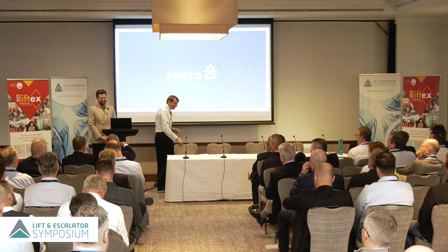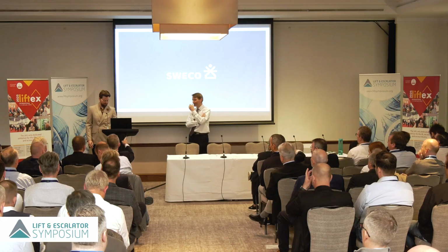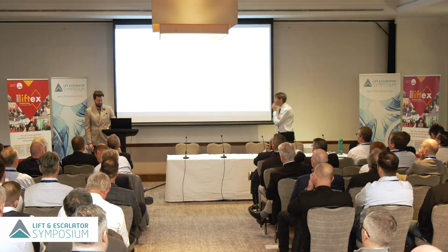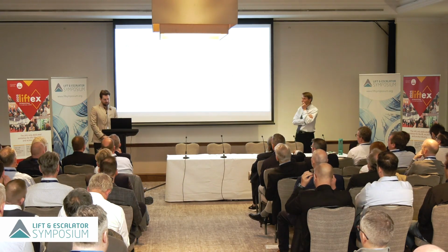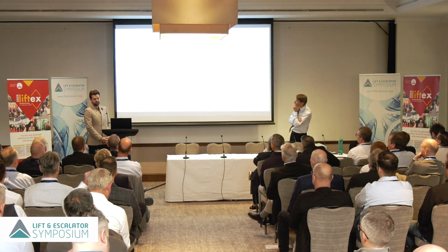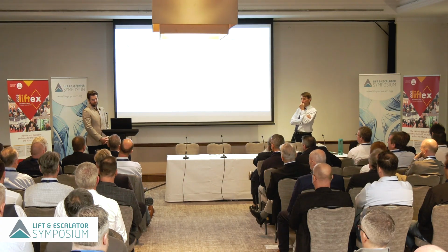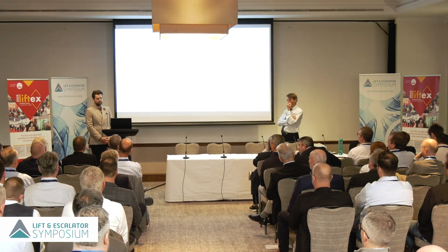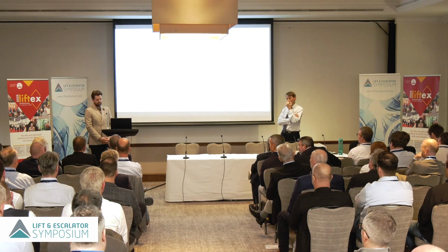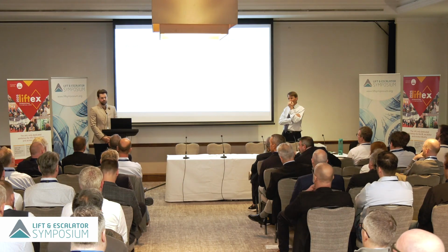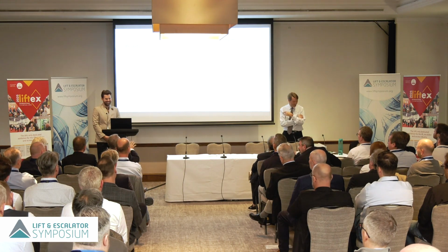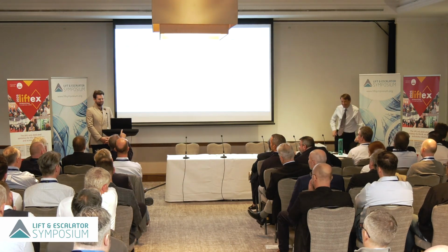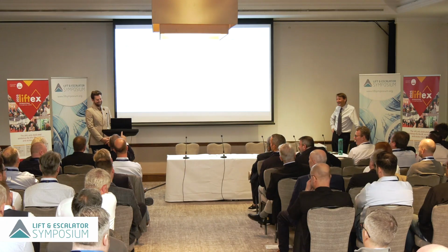Thank you very much. Do you mind if I use your slide to illustrate something? If you go back to your spatial plot. Okay, see that first one, you stop at 34 and 33. I bet the first time round, your lift is full and it doesn't need to stop at 33. It is, yeah. But it's the point I was making. You've got to know whether or not to stop. And of course, we don't know, the lift is weighing the number of people in the car, and that doesn't necessarily correspond, and the bypass is not necessarily set at exactly the right level. You can fiddle it so it works. Yeah. Well, I'm just trying to explain to you. So this is where we can do better than that.